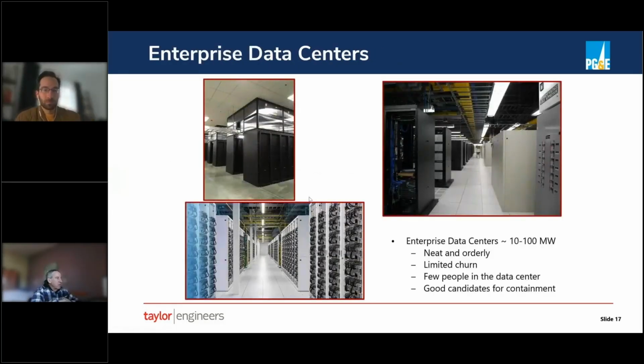Circling back through this list again, enterprise data centers have rows and rows of racks of computers, sort of like pizza boxes in a baker's rack. A typical rack will have 42U, which is the height definition of a computer. This is one of the old data centers we worked on a long time ago. It didn't have any type of containment, and it was underfloor. This is a somewhat newer enterprise that has containment. We'll talk about what that means. And this is a very recent one that we're working on that's liquid cooled. All of these little tubes are liquid cooling to the computers in each of these racks.